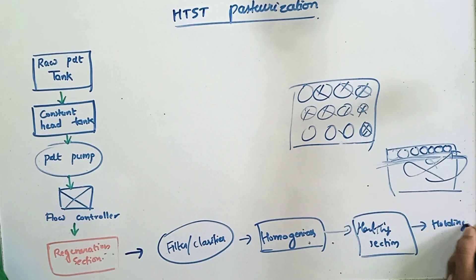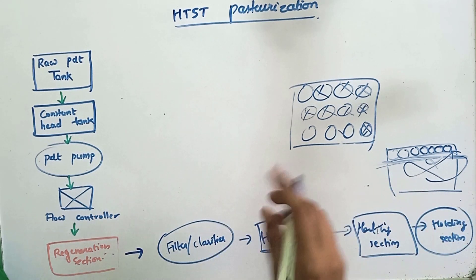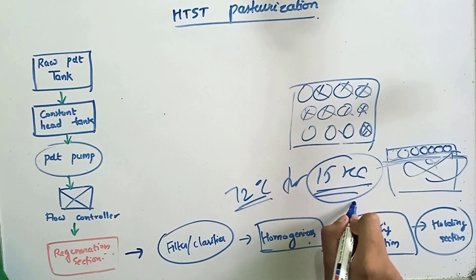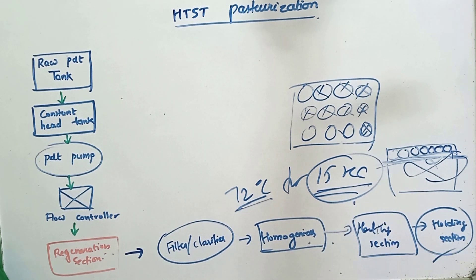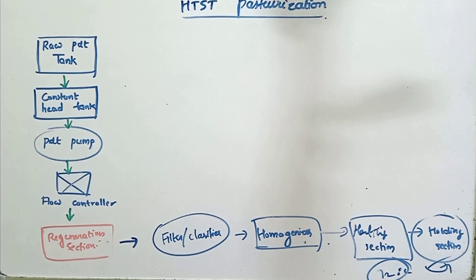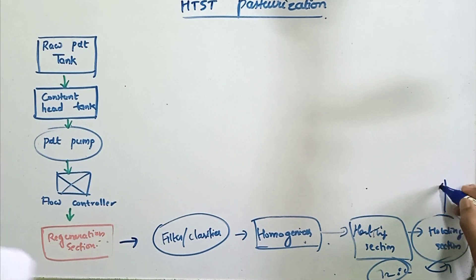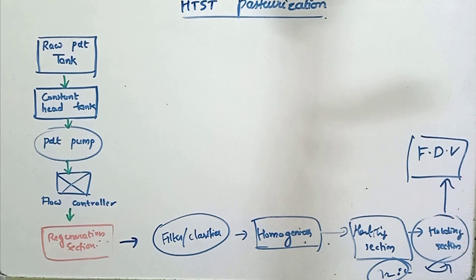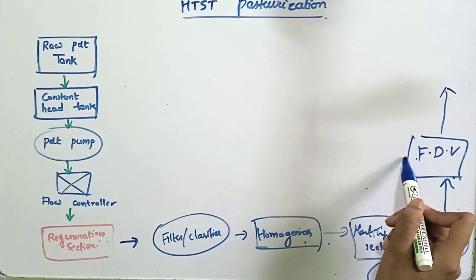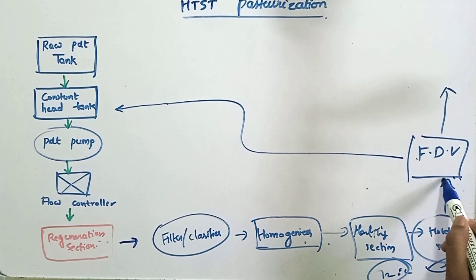The next one is the holding section. In HTST pasteurization, the milk is heated at 72 degrees Celsius for 15 seconds, so we must hold the milk at this temperature for 15 seconds — that is the purpose of the holding section. After holding, the milk is passed into the flow diversion valve. If the milk is properly pasteurized, it flows into the next section. If not properly pasteurized, the flow diversion valve returns the milk back to the constant head tank and the process repeats.